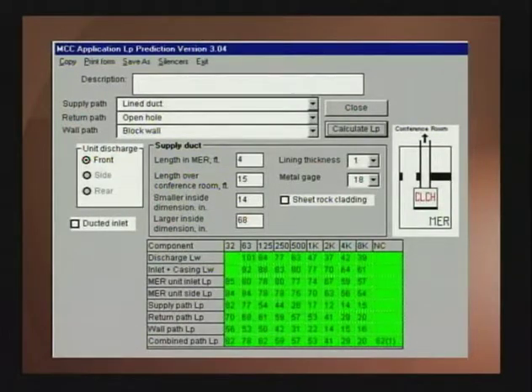Then there's a section of the form where adjustments can be made to the supply duct geometry to make it match exactly what's being modeled. The values shown on the form to start with are the experimental values that were obtained during the testing. Then the output form shows the discharge and inlet plus casing sound power levels, octave band data from 63 hertz to 8,000 hertz.